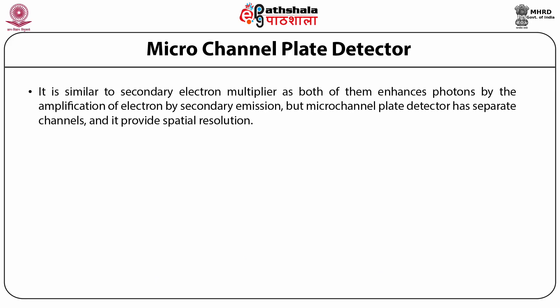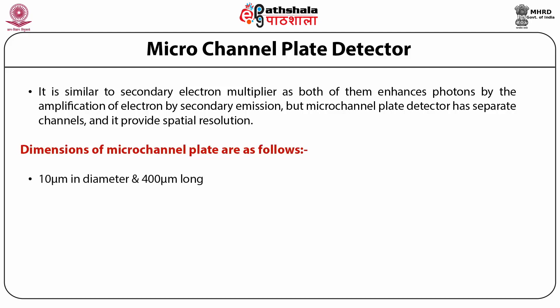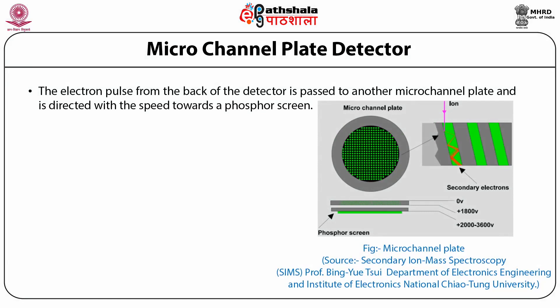The Micro Channel Plate Detector is similar to the secondary electron multiplier in that both enhance photons by the multiplication of electrons through secondary emission. However, the micro channel plate detector has separate channels and provides spatial resolution. Its dimensions are 10 micrometers in diameter and 400 micrometers long, angled at 7 degrees from the perpendicular to the surface plate, located at a 12-micrometer pitch. The electron pulse from the back of the detector is passed to another micro channel plate and directed towards a phosphor screen where it is detected.